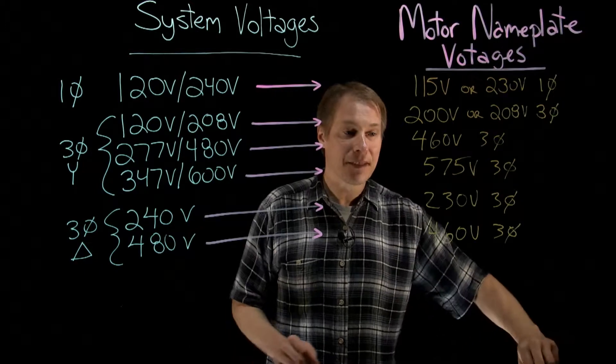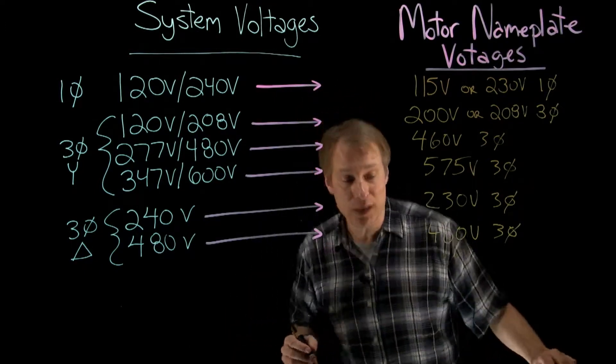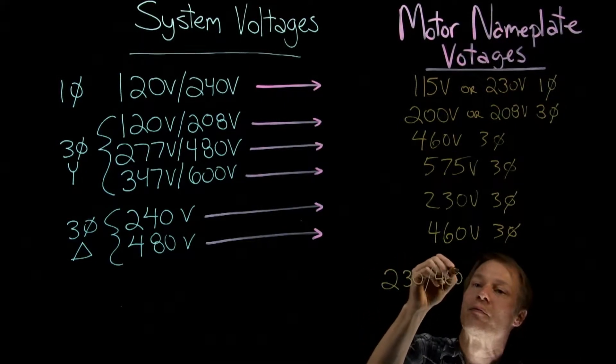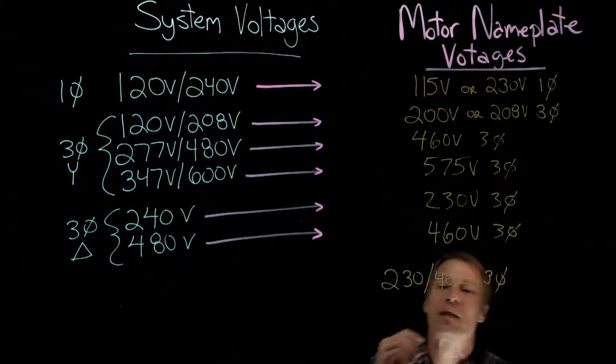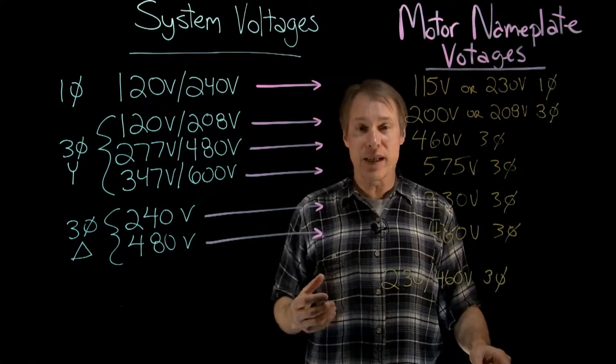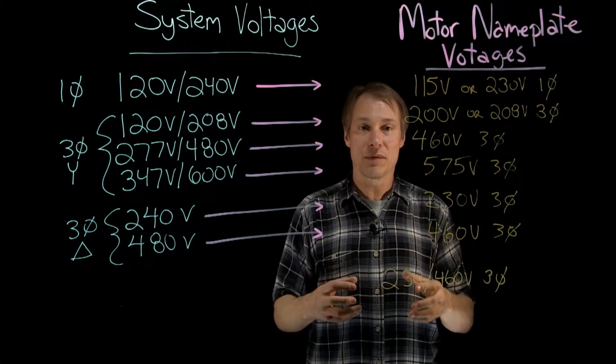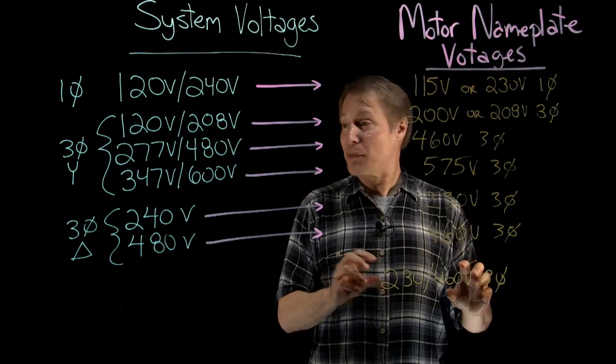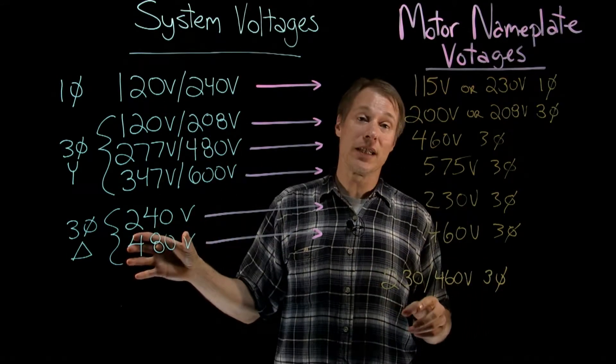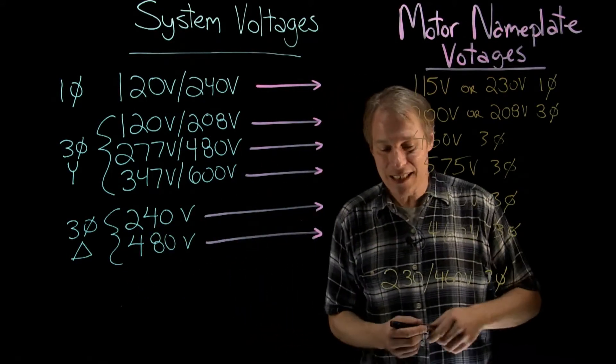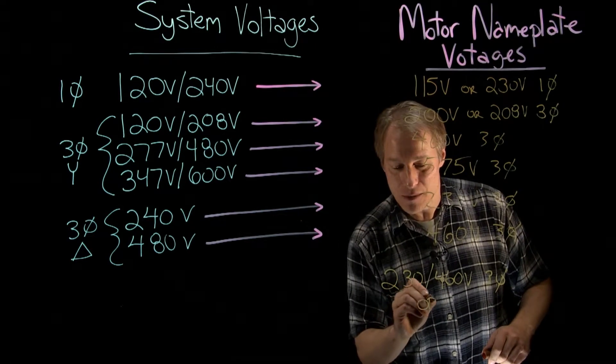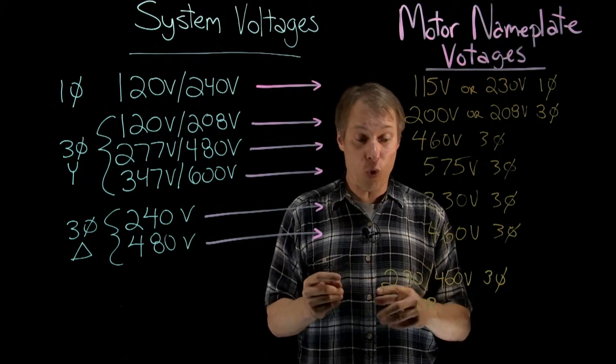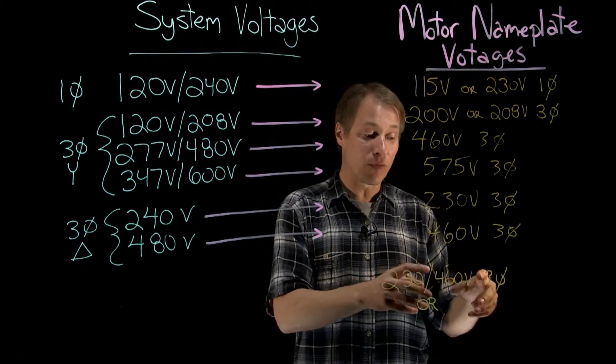The only other thing to add is some motors are dual voltage. So for example, I might buy a motor and on the nameplate it says 230V/460V three phase. So first of all, that is not a system. There is no 230V/460V system. What it is, it is a choice. So, you can either connect the motor to be rated for 230V or connect the motor to be rated for 460V.